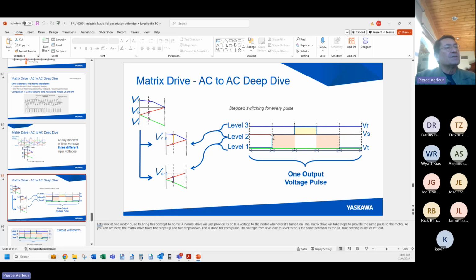So our pulse looks like, here's 0. We take the first step up. We take the second step up, which is the full height. Then we step down again, and then we step back to 0. This is one output voltage pulse of a matrix drive. Instead of the full height pulse with its attendant full height spike, we step up. And we reduce the dVdt significantly, which is why matrix drive claims we don't need output filters on long motor lead lengths. Our dVdt is much less. It's what we claim.